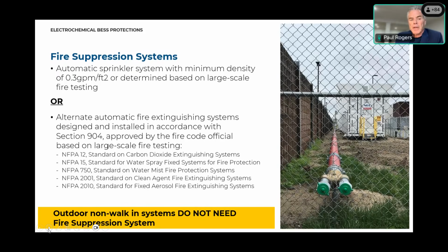And if you're putting in a sprinkler system, the minimum amount that you need to put in there is 0.3 gallons per minute per square foot, or determined based on the large scale fire testing. So if you want to go lower than that, you have to prove it by showing that the large scale fire testing actually can do that. If the large scale fire testing says you need to go higher than that, then you have to be based on that too. So that is just some guidance that the committee put out there, and it's important that you know that.